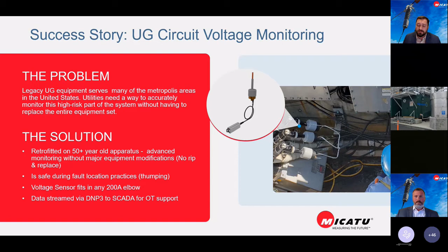The bushing -- the copper piece that's inside of the bushing -- fits in, connects into the elbow, and we're able to pull, as Adam alluded to earlier at a high level, the voltage measurement all optically. If you can see the cable coming out of the sensor there, that's all just a fiber optic cable. We measure using the E field that's generated on the inside of the sensor, and each one of these sensors has a little bit different form factor. But inside of the gray cylindrical area there is an E field generated with a bulk optics sensor.